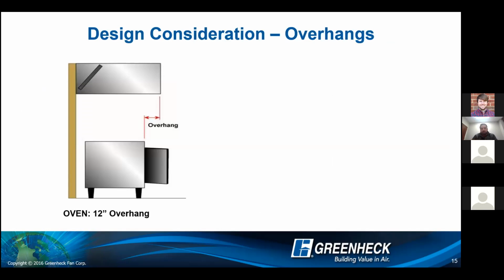The next design consideration is your overhang. As I mentioned previously, the minimum overhang from the edge of an appliance where it's an open side is 6 inches. So if you had a wall on the right-hand side of your hood, you could go right up to the edge of that wall. There wouldn't be any minimum on that side because it's a closed side. Or if you have a full end skirt, it's 0 inches from the edge of that hood. But if you have no end skirts, then it's always from the front, your minimum is 6 inches, which is all fine and good. And it works just fine.